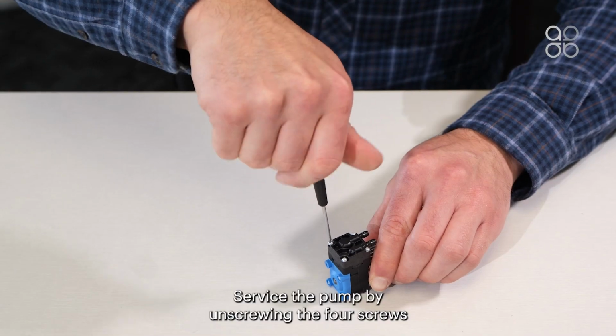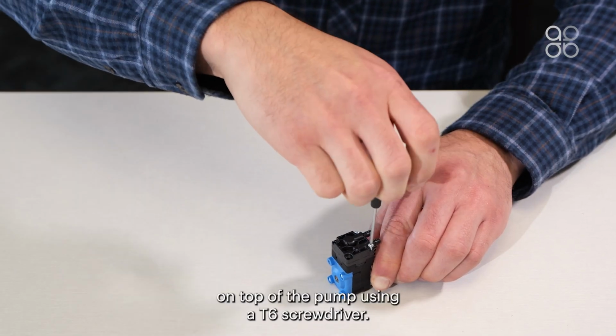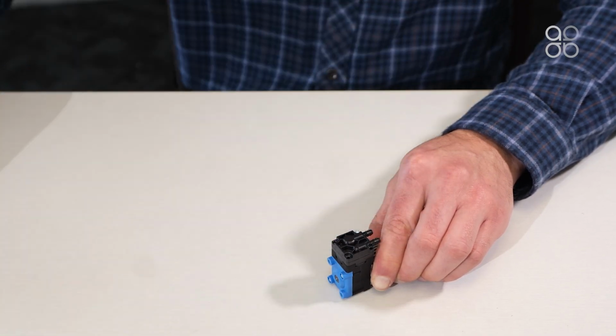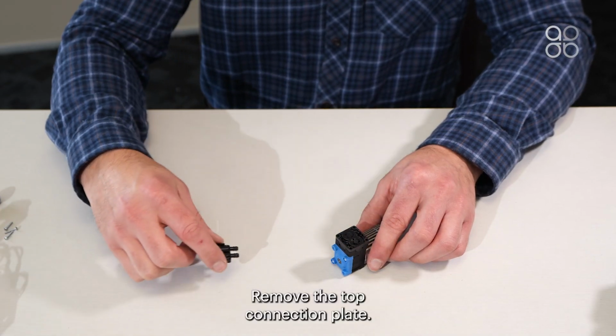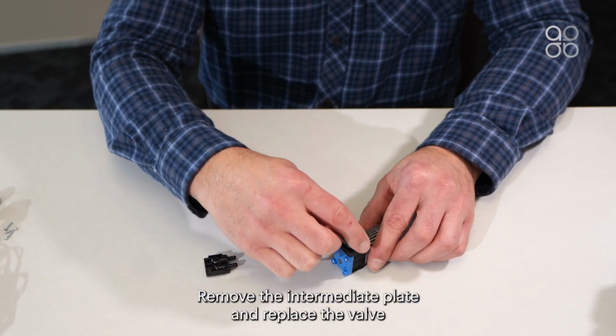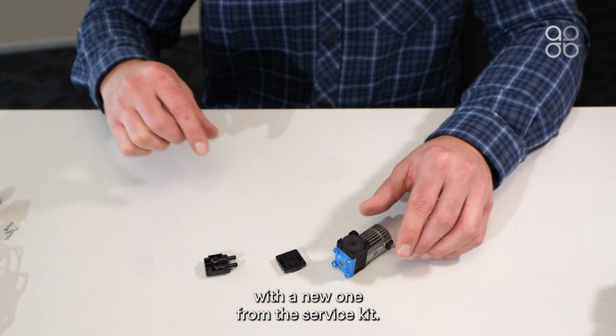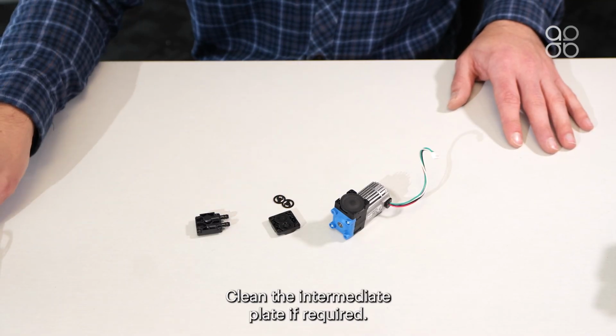Service the pump by unscrewing the 4 screws on top of the pump using a T6 screwdriver. Remove the top connection plate. Remove the intermediate plate and replace the valve with a new one from the service kit. Clean the intermediate plate if required.